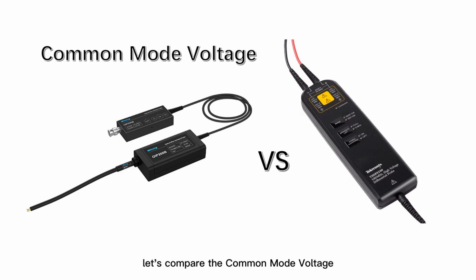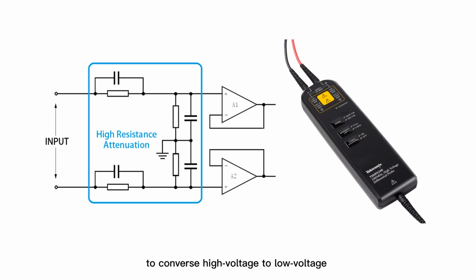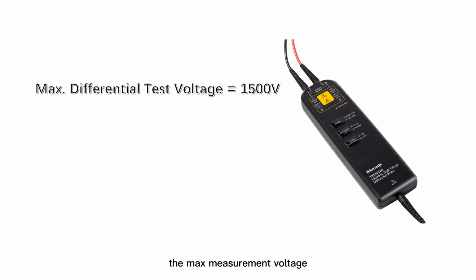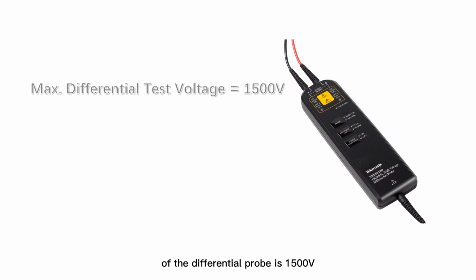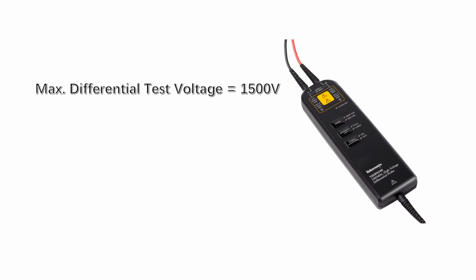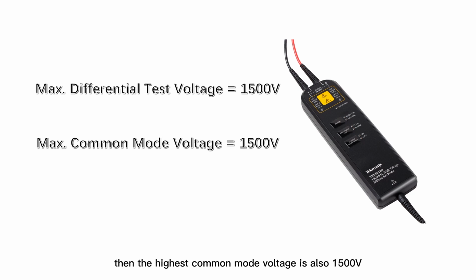Next, let's compare the common mode voltage. High-voltage differential probes use large-value resistors to limit the current, converting high voltage to low voltage. The measured differential mode voltage is therefore the highest common mode voltage. For instance, if the max measurement voltage of the differential probe is 1500 volts, then the highest common mode voltage is also 1500 volts. Common mode signals above this voltage cannot be rejected. That could endanger equipment and personal safety.